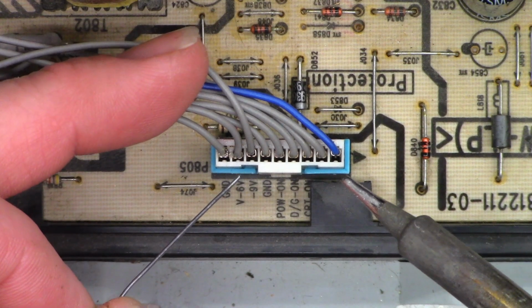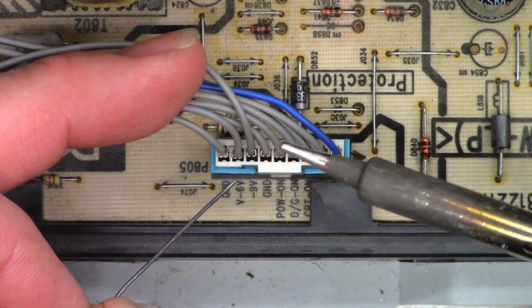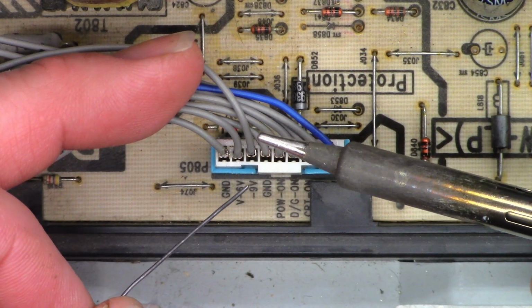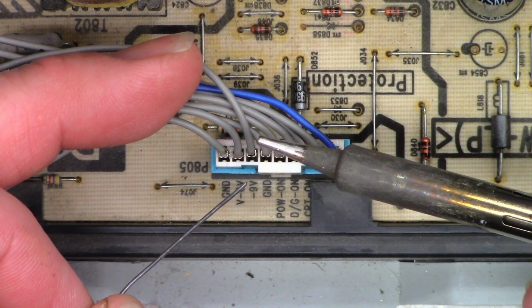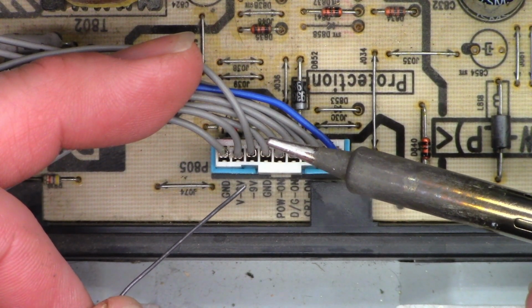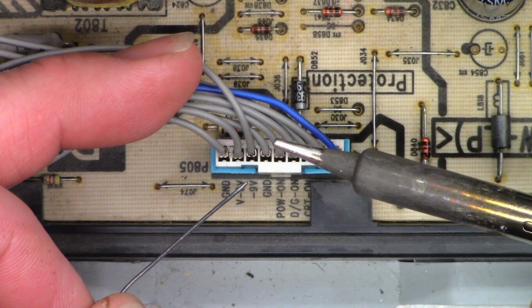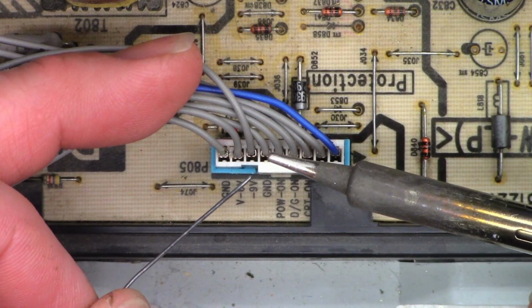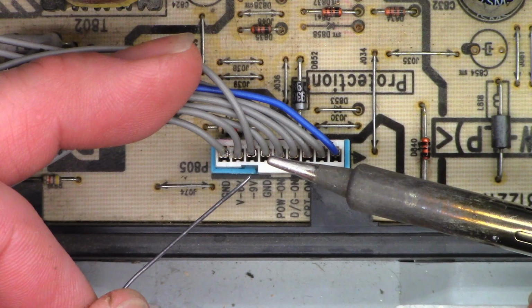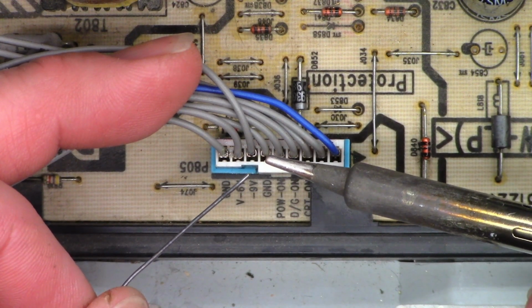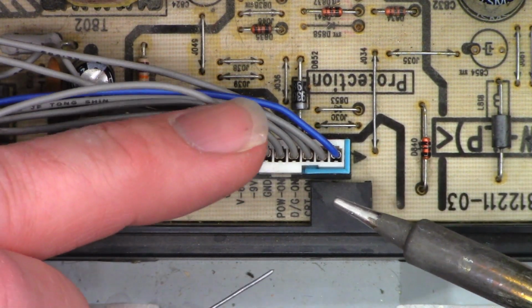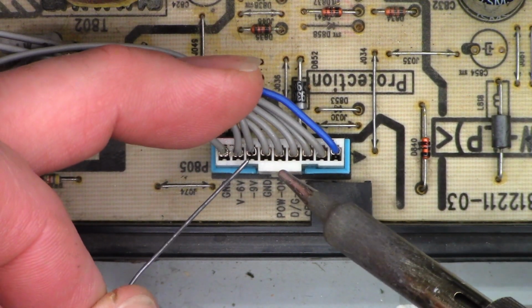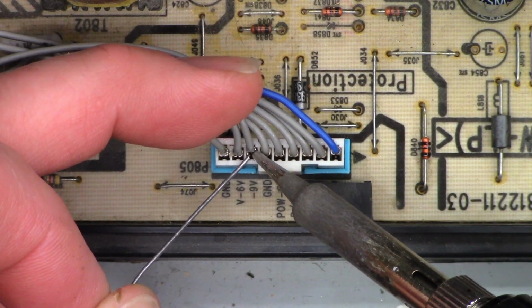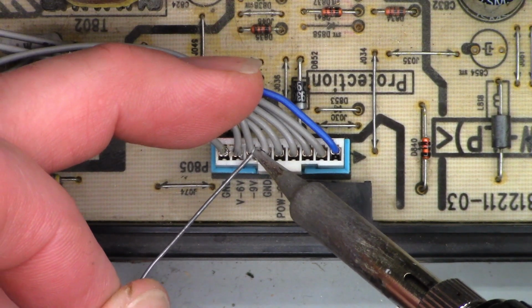So power is removed, by the way. And incidentally, if you're curious, the tip on this unit is not grounded to earth. It is earthed slightly through a 1 million ohm resistor, so that if I do accidentally contact a hot lead with this while it's on, it won't do any damage. So I do that typically mainly for ESD, electrostatic discharge.